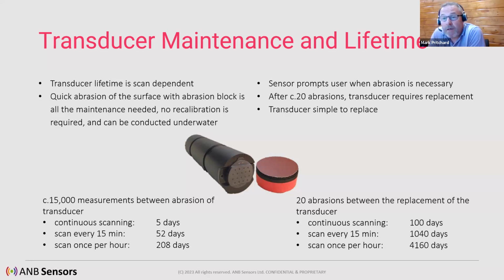Every 15 minutes, it's over 1,000 days, 1,040 days. But the sensor will tell you when it needs doing. They're intelligent in that respect. You won't have to keep a calculation of, if I'm sensing every 15 minutes, how long do I need to go before abrading? It will tell you when that's required. And that's output, whether we're on the RS-232, RS-485 in serial or in Modbus. It's all provided to the operator.